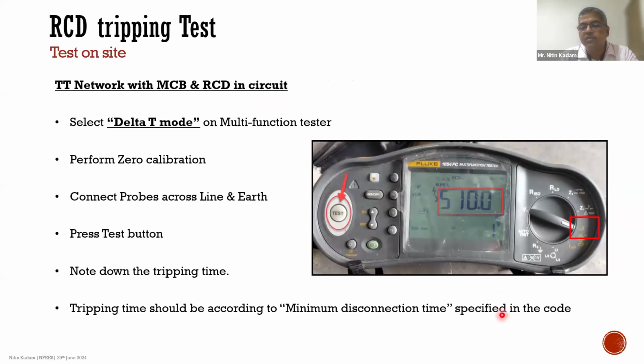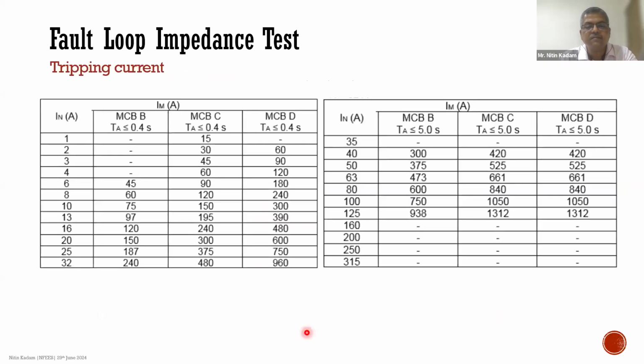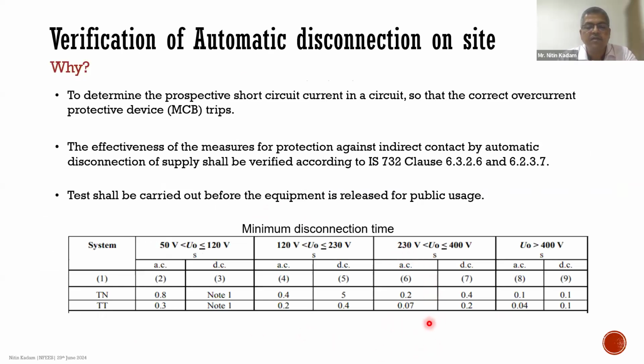In case of TT network, as I was mentioning earlier, MCB is a must as well as RCD is a must. And in the case of TT network, it is required to measure the tripping time of the RCD and not the fault loop impedance values or the fault loop impedance current values. So this knob has to be turned into the delta T mode, which is the tripping time mode on the multifunction tester. Perform the zero calibration, connect the probes on the line and the earth terminal, again press this test button and note down the tripping time in milliseconds here. And this tripping time should be according to the minimum disconnection time that is specified in the code. I'll just go back to the slides. So this is the chart we have to refer, which is available in the code. And these are the values which we have to adhere to.